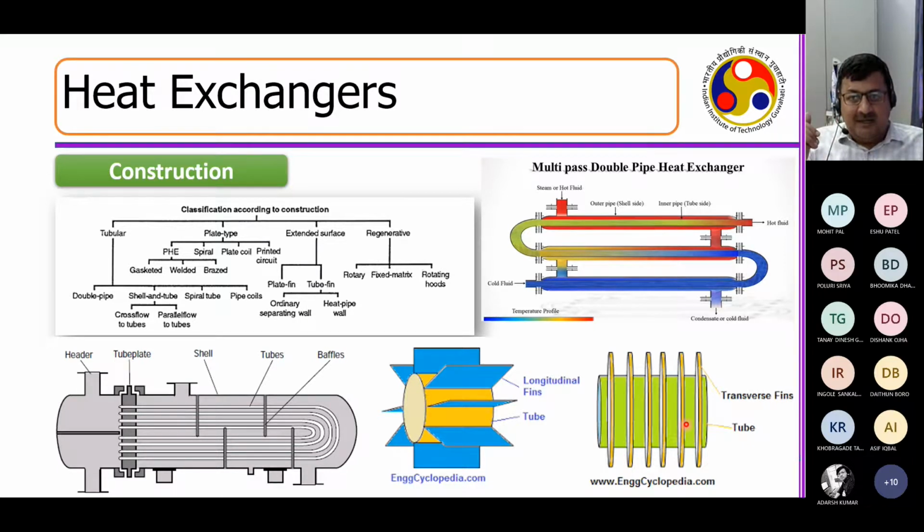So here, with this type of pipe and tubing, I ensured that the heat transfer coefficient is increased with this type of fins on the tube. Now, when I put fins, you know that when the fluid is flowing through this, it will also do crisscrossing. So again, I increase my heat transfer coefficient, and at the same time, I also increase the heat transfer area. In that process, a 1 kilometer long heat exchanger is converted into this small one, where I have similar efficiency.